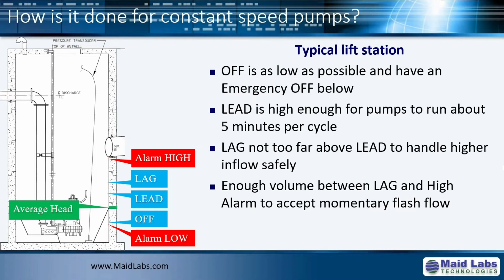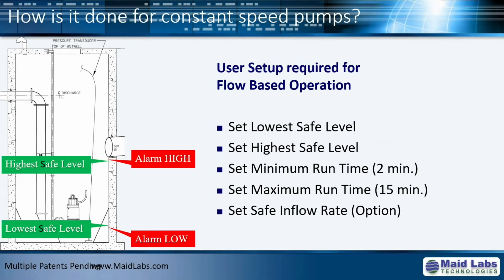so to use a flow-based operating system, you need to set what is the lowest safe level and what is the highest safe level. This is basically, when the flow rate is very low, how high would you accept the level to be? And when the flow rate is very high, how low can it be? And what is a normal minimum runtime for your pump and a maximum runtime for your pumps before you would alternate between each other? So that's the idea behind it.